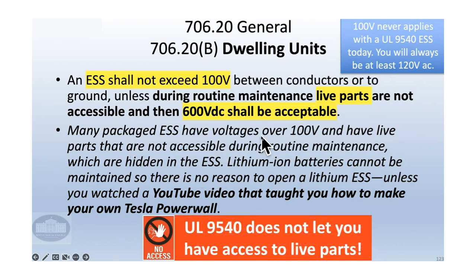Okay, so this is one of the more confusing parts of the code in Article 706, because it says an energy storage system shall not exceed 100 volts. And every 9540 listed energy storage system is 240 volts at least, or 120 volts even, because we're talking about AC. And then it says, unless during routine maintenance, live parts are not accessible, and then 600 volts shall be acceptable. I think that they just need to write this part of the code a little bit better. And so one of the things that you'll notice is when you see one of these energy storage systems, you don't go in there and do maintenance on the battery cells. You don't go in there and add a little bit of lithium when they start wearing out like you would with a lead acid battery, how you add distilled water.